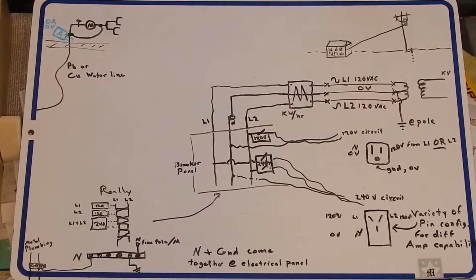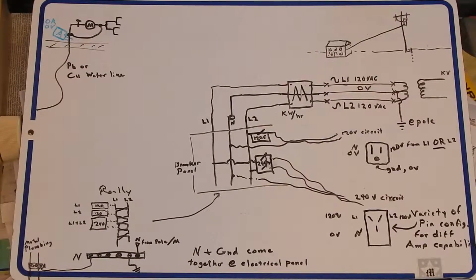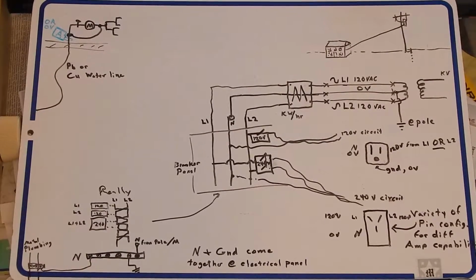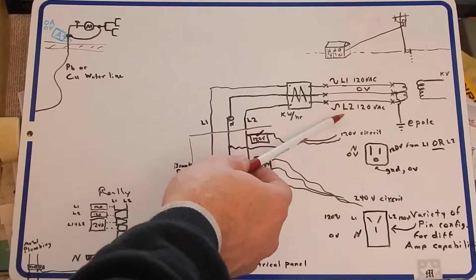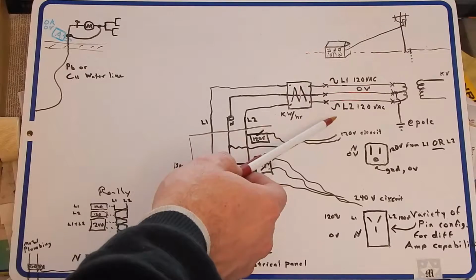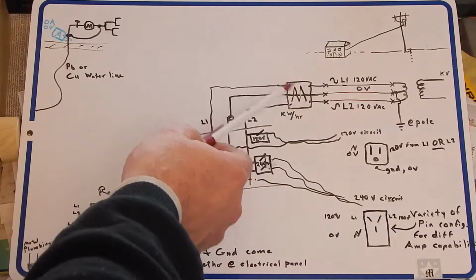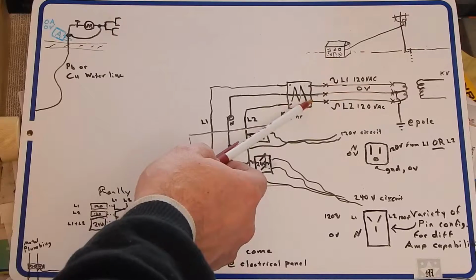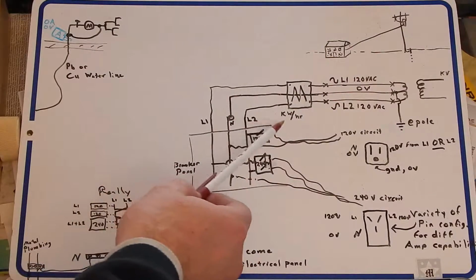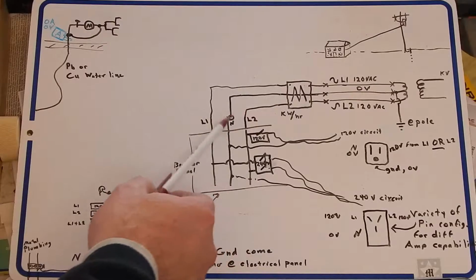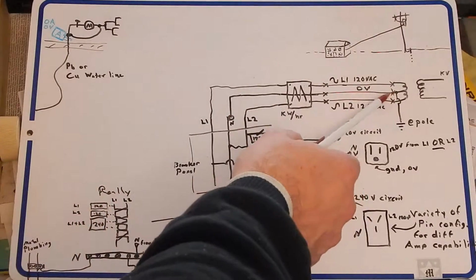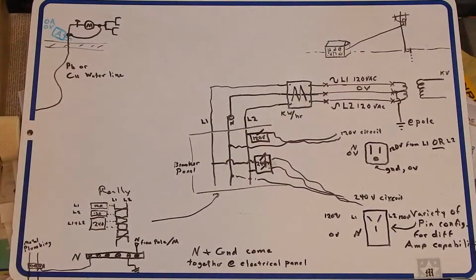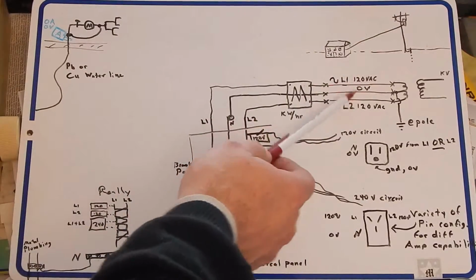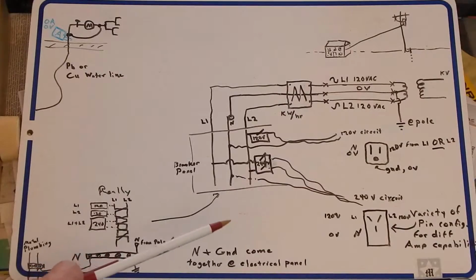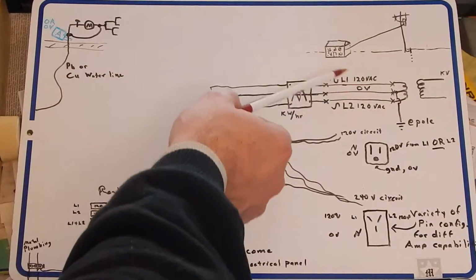I talked about a channel called the Burb Billy before. He recently posted a video on what happens when you lose one of your wires from the pole, or it could be in your meter box. You know, a terminal can burn up, or with corrosion, or otherwise get disconnected. There's also connections at your fuse box. There's also connections at the pole. Any one of those can go bad, making any one of these three wires go out. And he's covered the first condition, which is if one of these two come out.